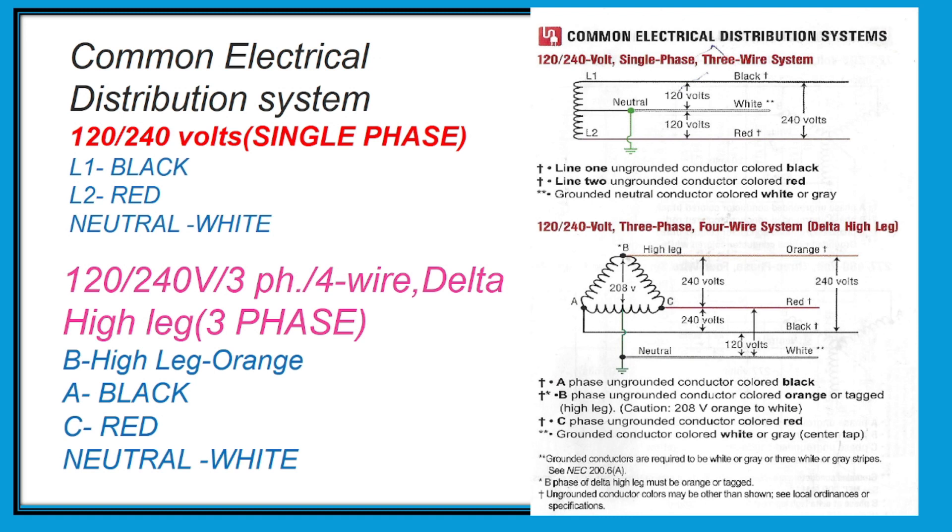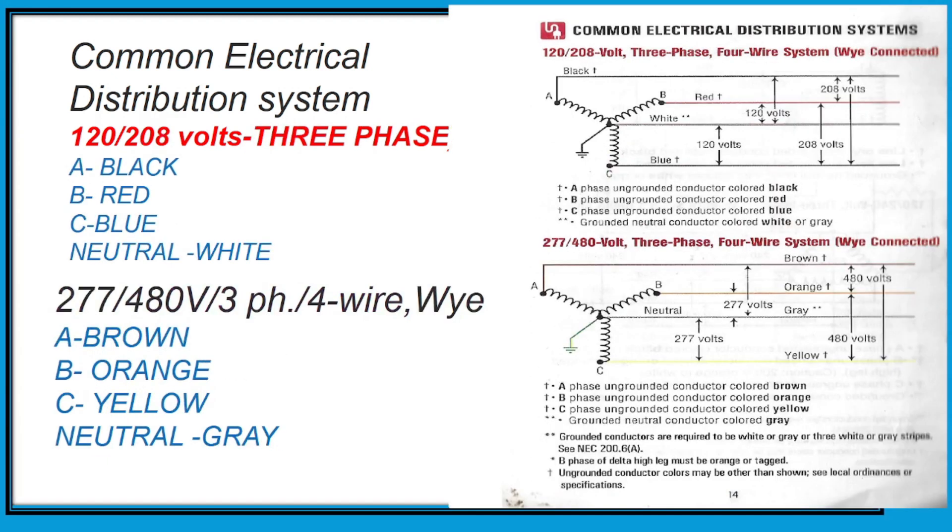We have also 120/240 volts three-phase four-wire system delta high leg. The next one is 120/208 volts three-phase four-wire system wye connected. Line 1 or A is black, line 2 is red, line 3 is blue, and neutral is white.